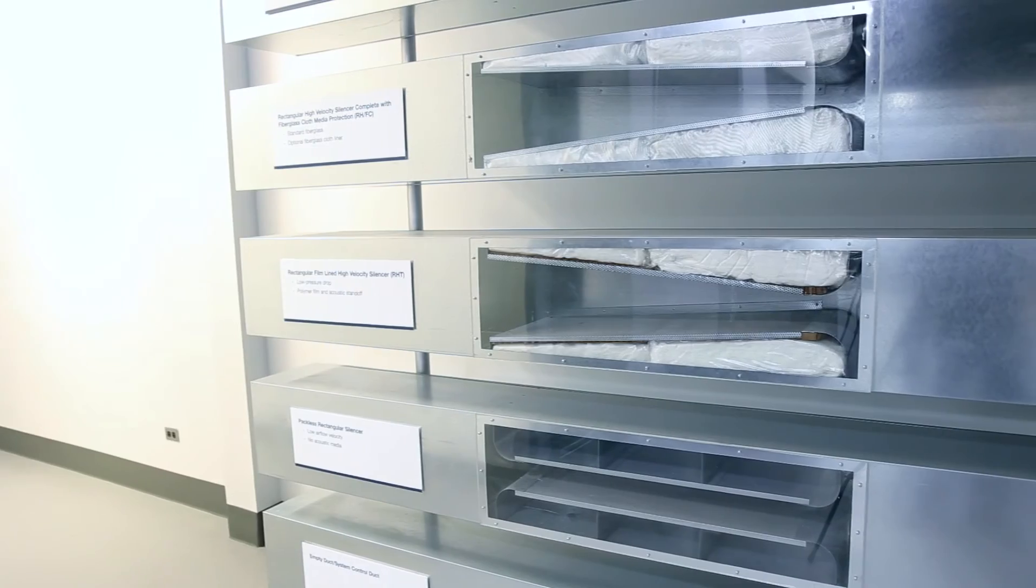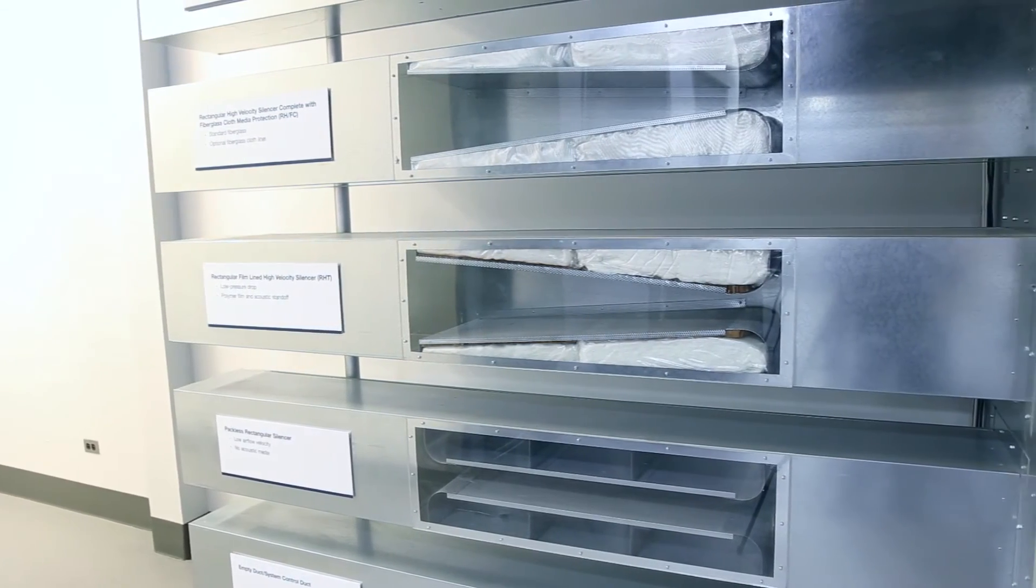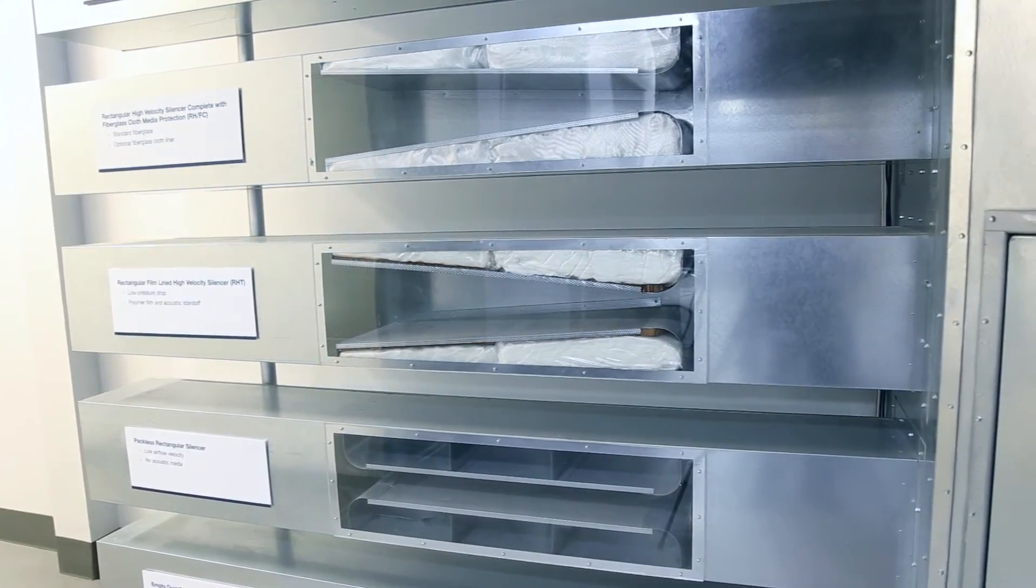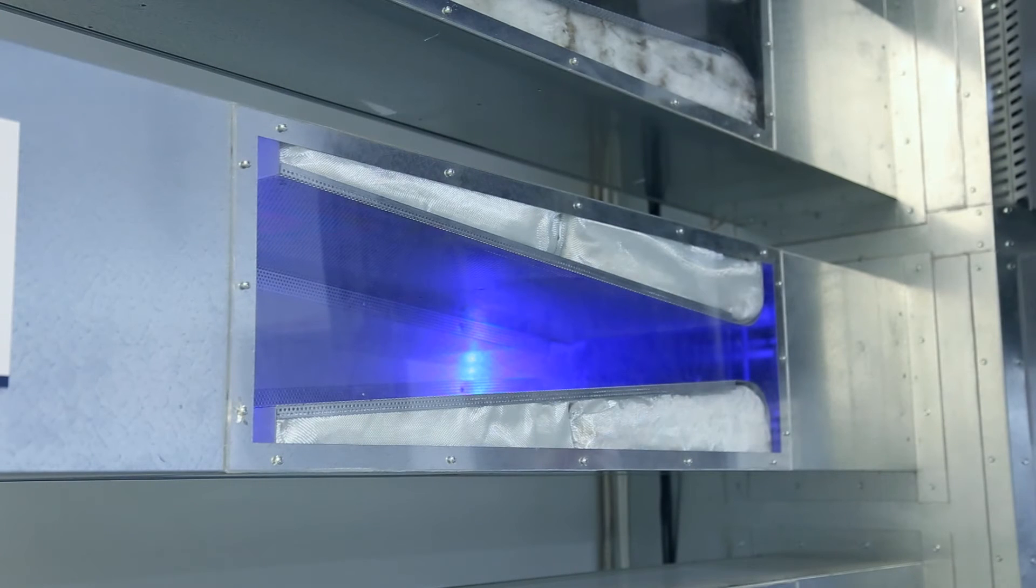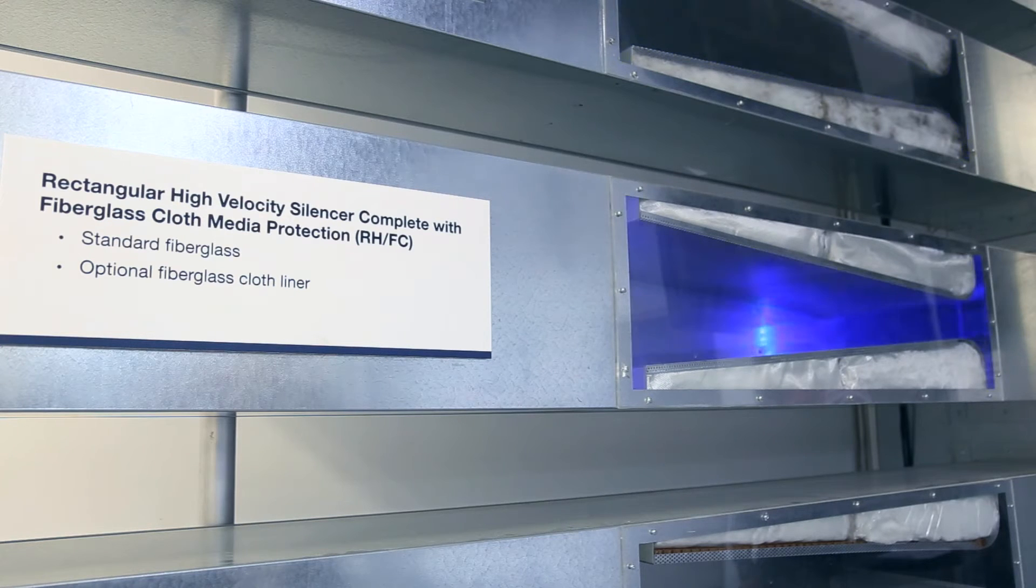The next three silencer examples are for different media options and liner types. The first silencer is a rectangular high velocity silencer with a fiberglass cloth liner. This fiberglass cloth liner protects the acoustic media from erosion and has very little effect on the acoustical performance.